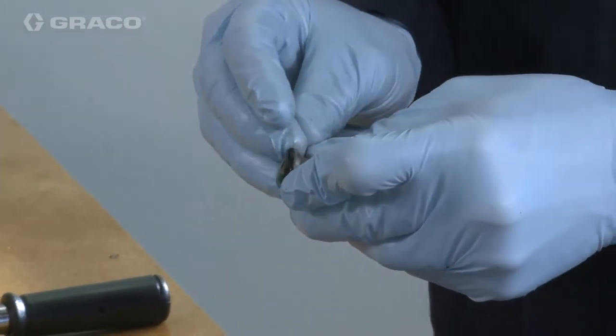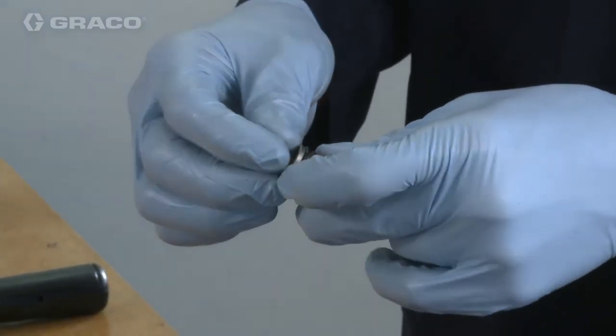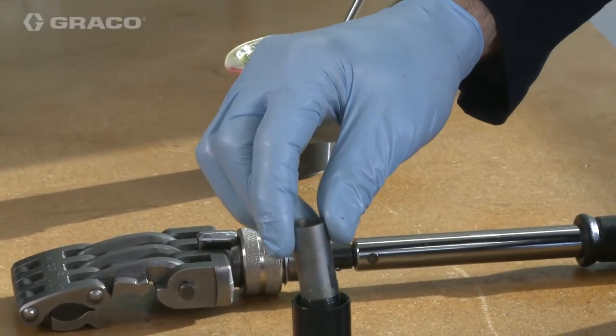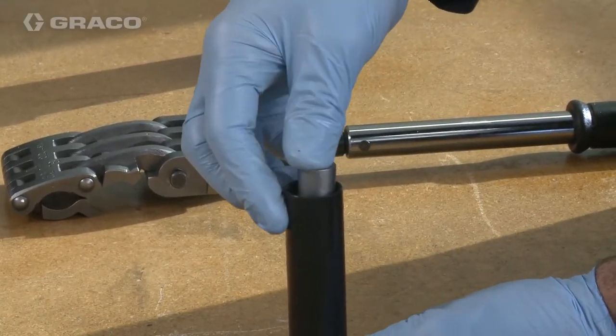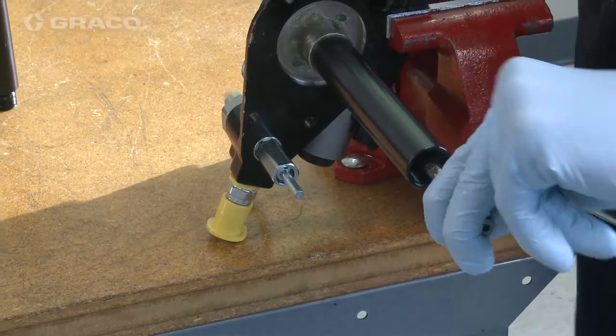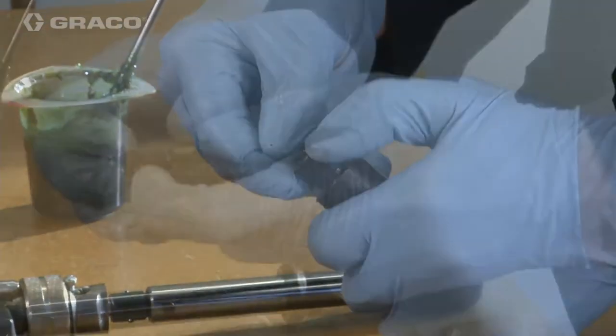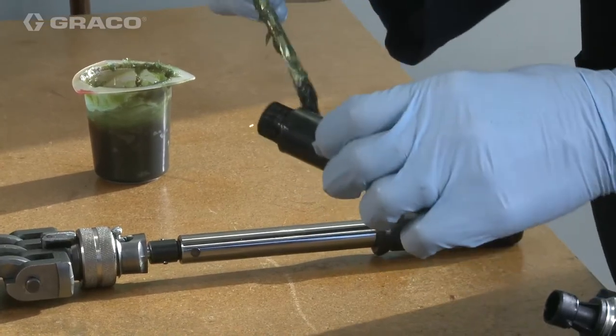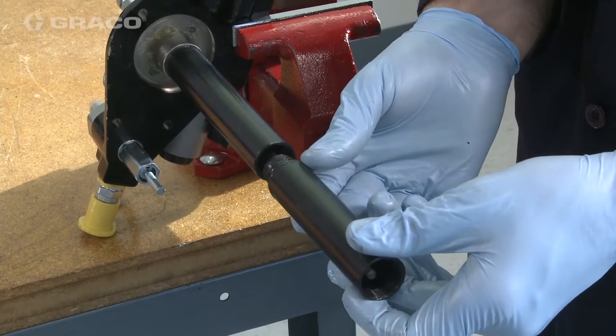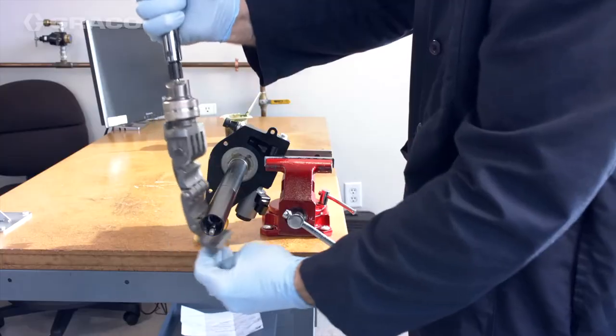Replace the two backup rings and o-ring with new backup rings and o-ring and lightly grease. Place the piston bushing into the pump lower tube until seated. Place the pump rod into the pump piston groove. Replace and lightly grease the o-ring on the lower pump tube. Slide the pump lower tube over the pump rod and connect to the extension tube. Torque to 30 foot-pounds.